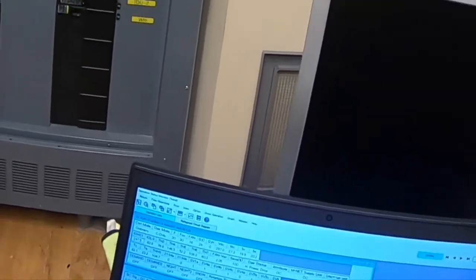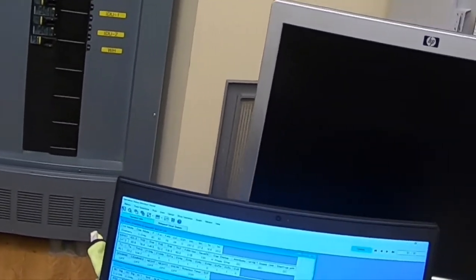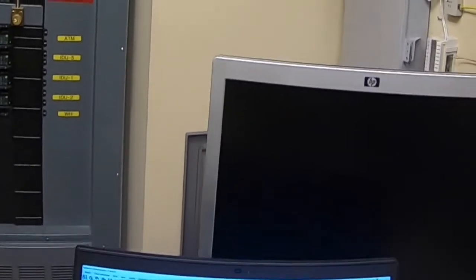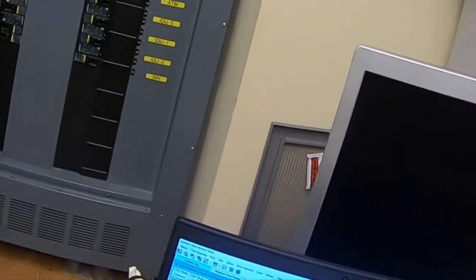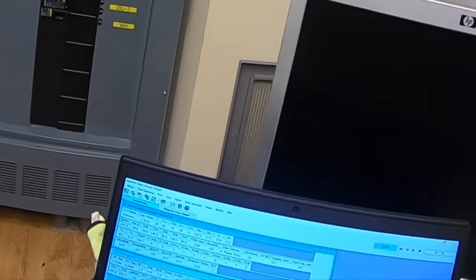This is the room I'm in right now, and I've closed the door, so the temperature will rise in here. After I run all of them for a little while in test mode, I'm going to take them out and put them in normal mode, because this room will heat up with the door closed, so I can get a good sense of if the server room is actually cooling like it should, and make sure it doesn't go back into the fault it was in.